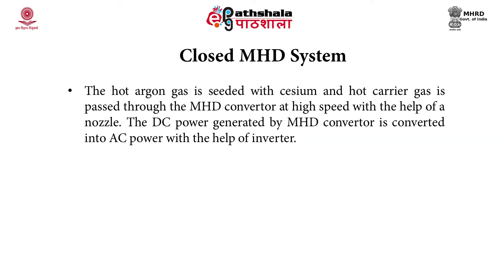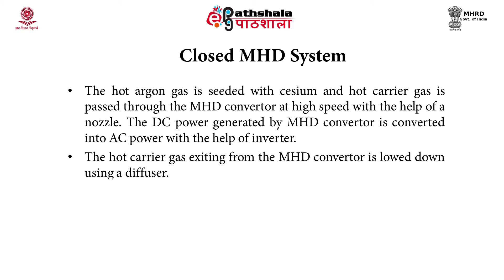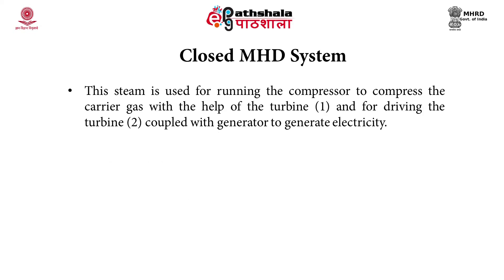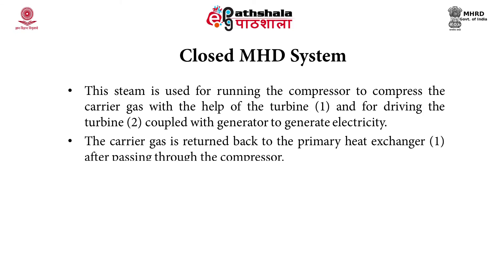The hot argon gas is seeded with cesium, and the hot carrier gas is passed through the MHD converter at high speed through a nozzle. The DC power generated by the MHD converter is converted into AC power with an inverter. The hot carrier gas exiting the MHD converter is slowed down using a diffuser, then passed through a waste heat boiler or heat exchanger to generate steam. This steam runs the compressor to compress the carrier gas and drives a turbine coupled with a generator to produce electricity. The carrier gas is returned to the primary heat exchanger after passing through the compressor.